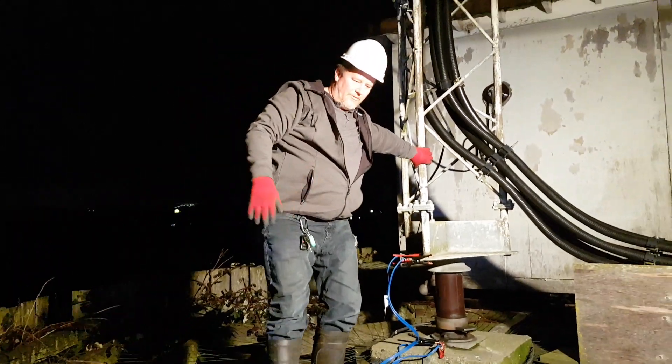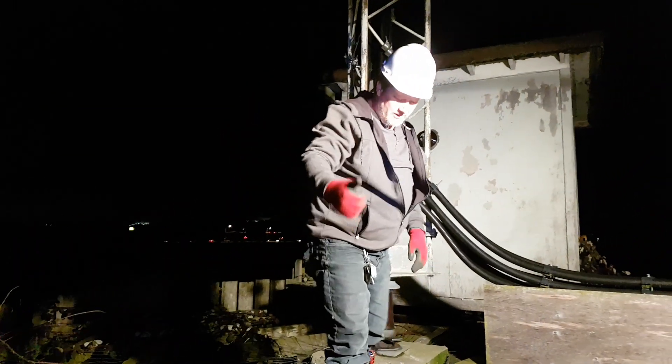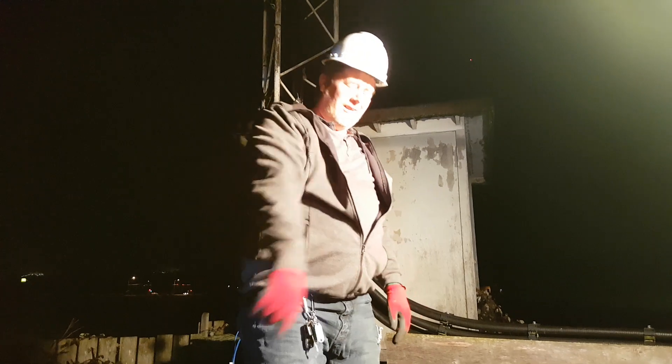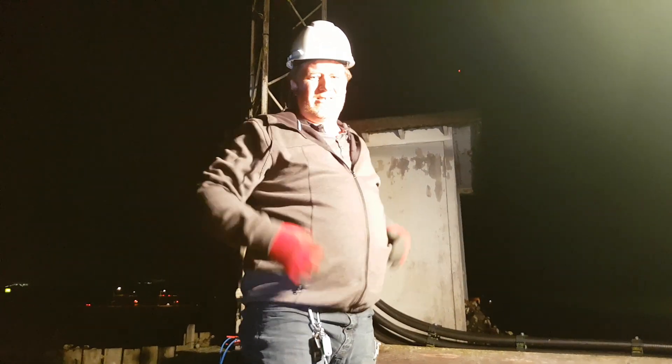The radial grid goes down over into the grounding. So he's blocked the transmitters, turned off the breakers, and for backup we've also grounded the tower. Now we're good to go and work on the induction coil where we know there's a fault inside. Let's go take a look in there.